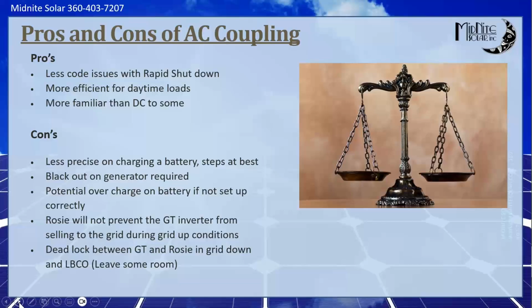So what I like to do on an AC coupled battery backup system is set my low battery cutout a little higher than I normally would. Then when the customer calls and says, hey, I'm experiencing this problem, you can say, okay, turn the Rosie off, turn it back on, and it will boot up and make power, and the grid tie inverter will come back on. Now keep an eye on your usage and don't overload it. That's just something to be aware of. Most battery-based inverters will have that issue.